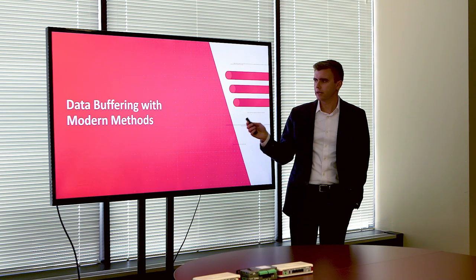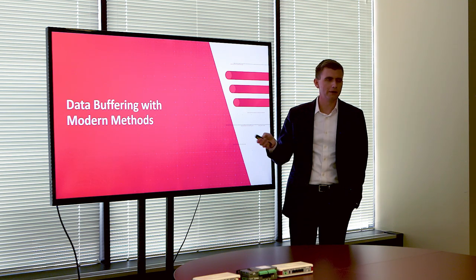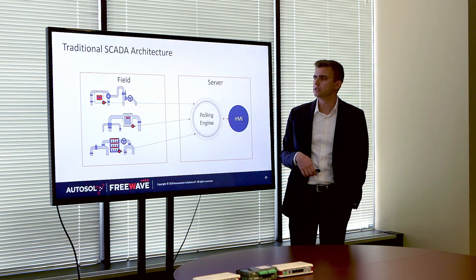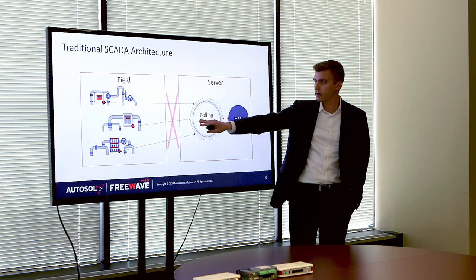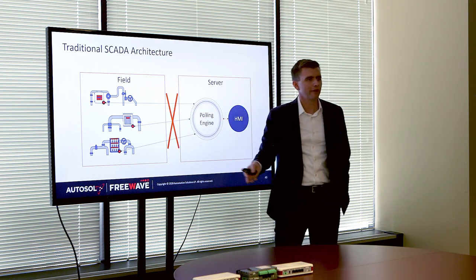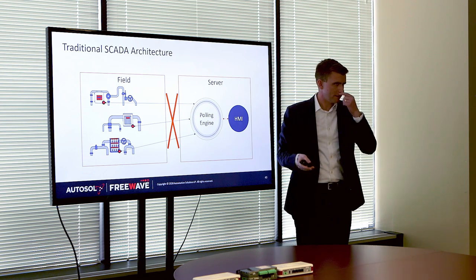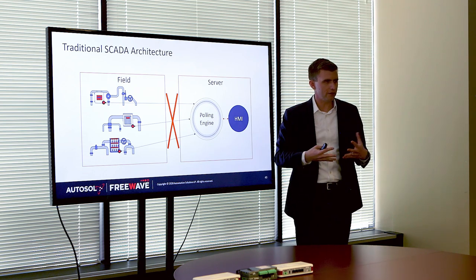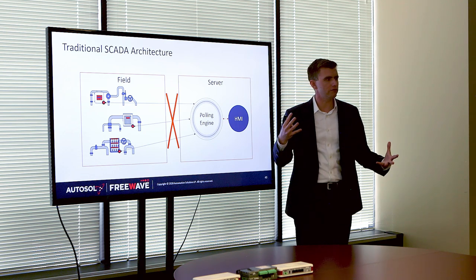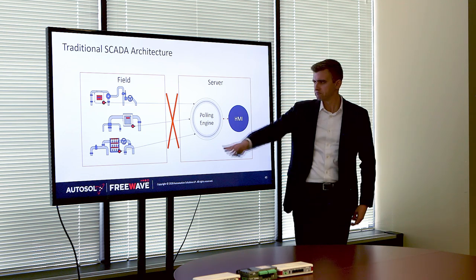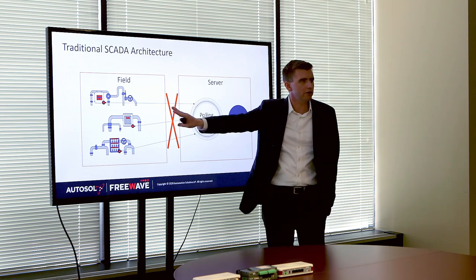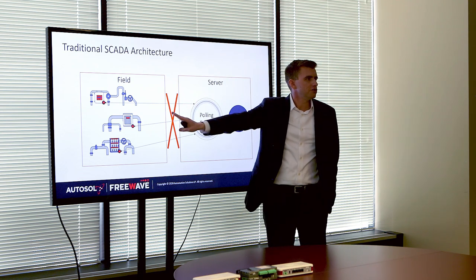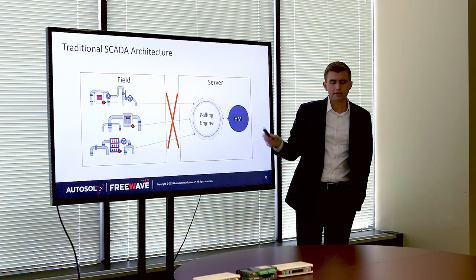The other case is data buffering with modern methods — Edge ACM with MQTT. In traditional SCADA, if you lose connection between the field and the server, unless you're using DNP3 or have a very elaborate method set up for extrapolating real-time data from historic data stored on the device, you've missed that poll. If there's fog, pine trees, or whatever, and you've lost communication to the field, chances are your HMI is going to miss that data.